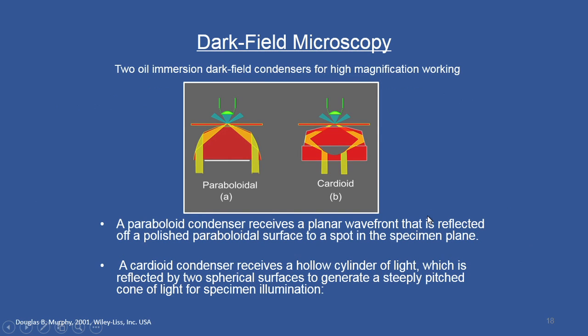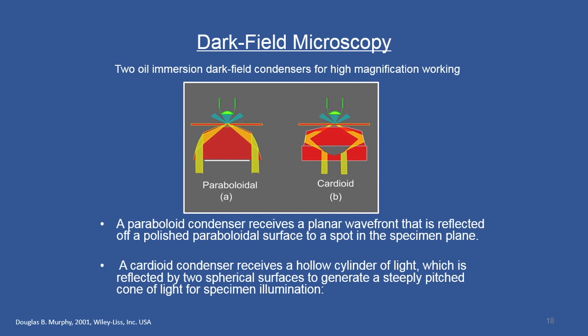This is a very simple design and very sensitive technique, because images based on small amounts of diffracted light from minute phase objects are seen clearly against a black or very dark background. If the numerical aperture of the objective is lower than that of the condenser and the dark field annulus, non-diffracted waves are excluded from the objective. You can have two kinds of oil immersion dark field condensers for this optical setup.